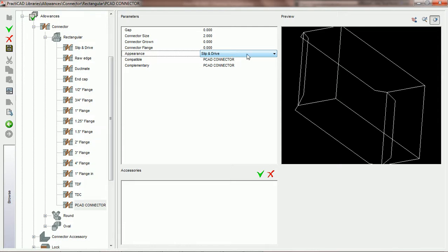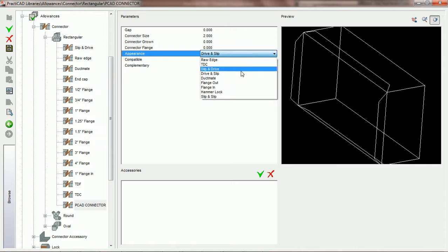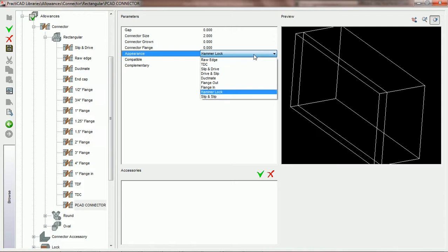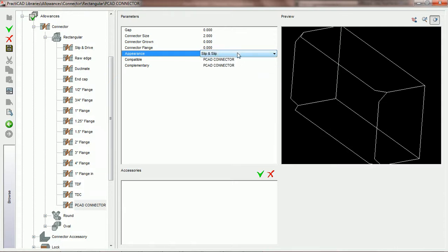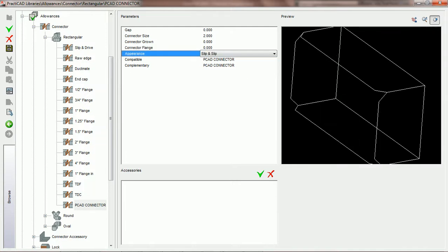You can see here that we've got the appearance set as slip and drive, but we also have the ability to switch appearance to TDC, drive and slip, flange in and flange out, hammer lock, and slip and slip. The only time the appearance will not actually preview, as you see here, is if in fact you have chosen a value for connector flange. Connector flange, as we covered in earlier tutorials, once you give it a value, PractiCAD basically puts an inside flange so that we can connect something to the inner part of it. However, anytime connector flange is 0, you will always see the appearance that you have listed in this particular option.